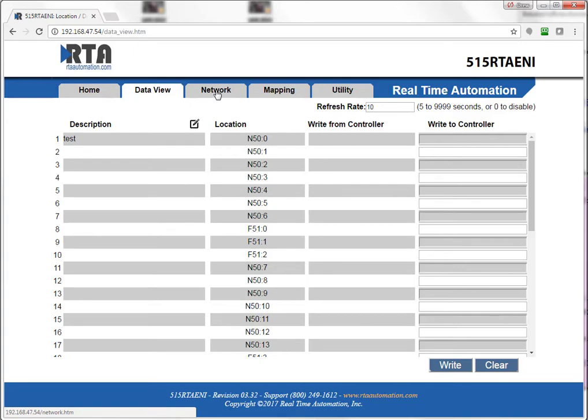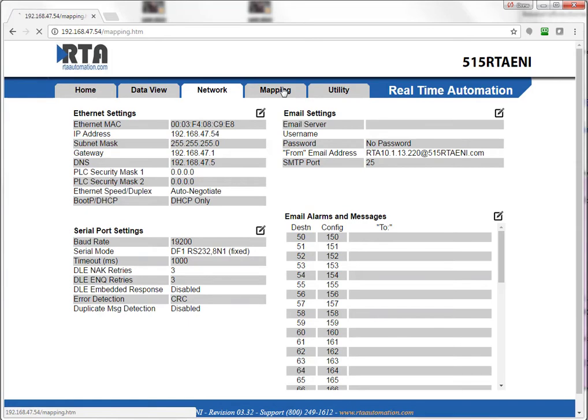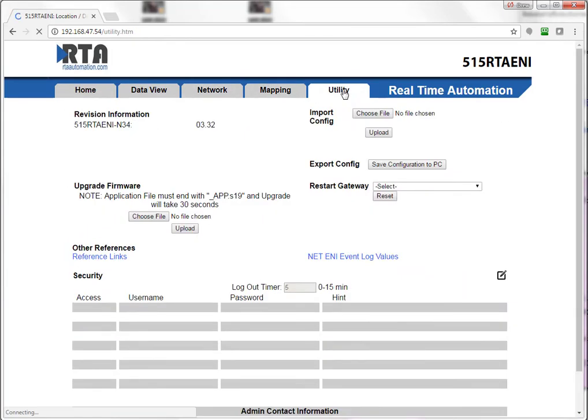Watch the save load and then revert back — that change has now taken effect. Network is the network settings. Mapping, while not used in all applications, is placed here. And then finally on the utility page, the two things that are probably most important are first, security. As this is all browser based, you may want to lock those pages down so people you may not want there don't get there. And then finally we have the load and save configuration. Once you do have a unit up and running, you can save that file off and put it into a backup unit on the shelf, or just have it for a later date in case it's needed.